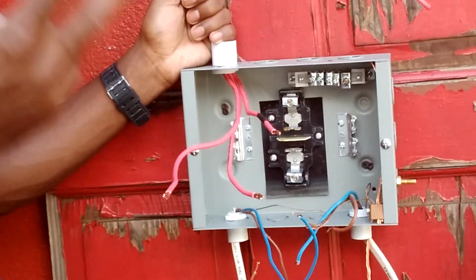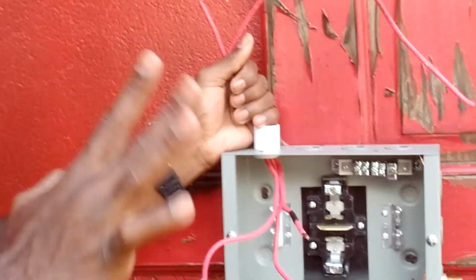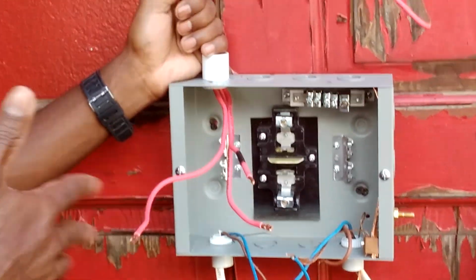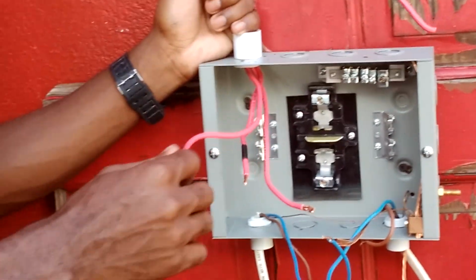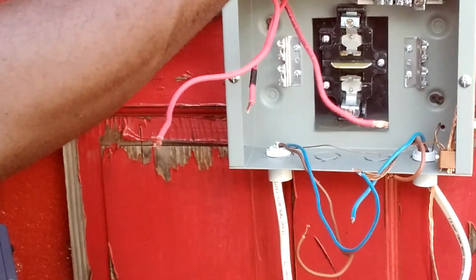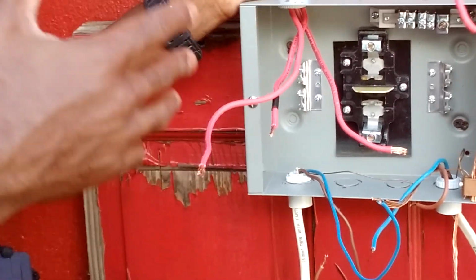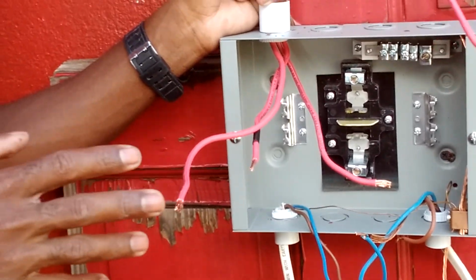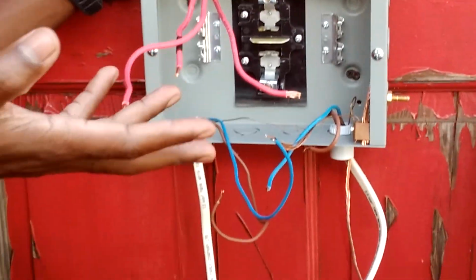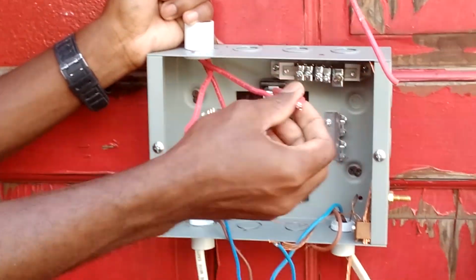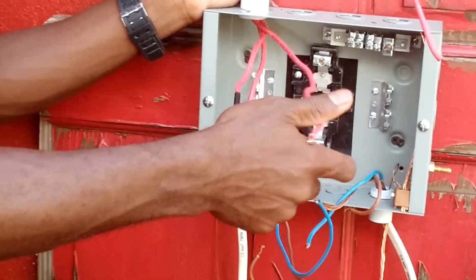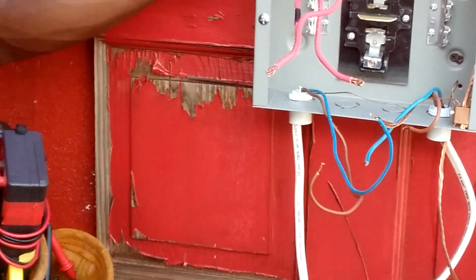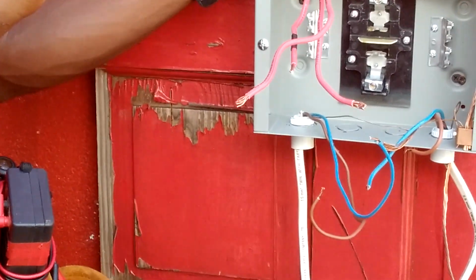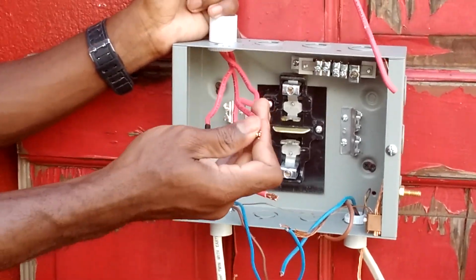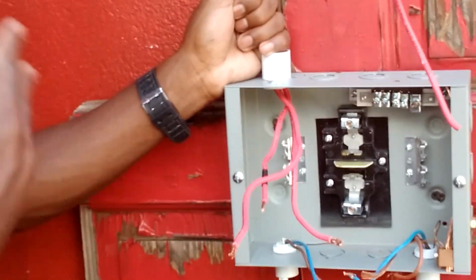The reason I use 2 live wires is because it's for a 220 supply. In the Jamaican system, or grid, for domestic purposes we have a grid of 110 or 220. When you use 2 hot wires, you get 220. If I use only 1 hot wire, you get 110. So today we want to wire this for a 220 supply.